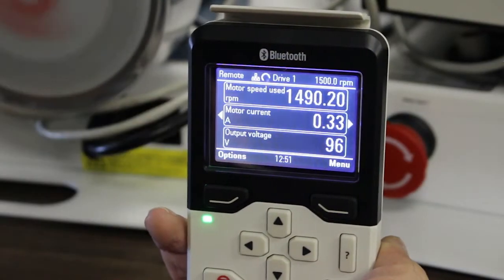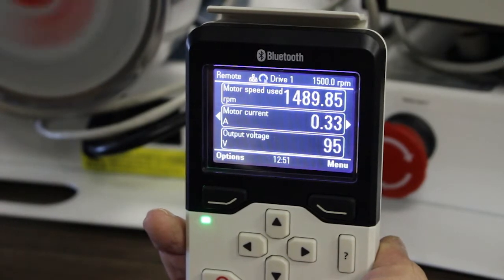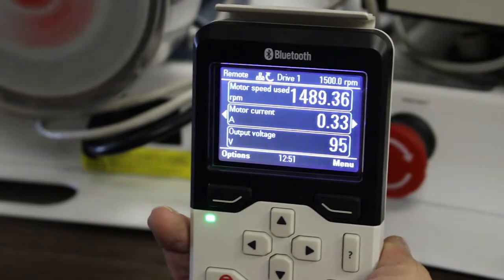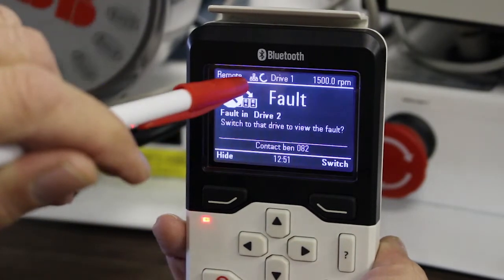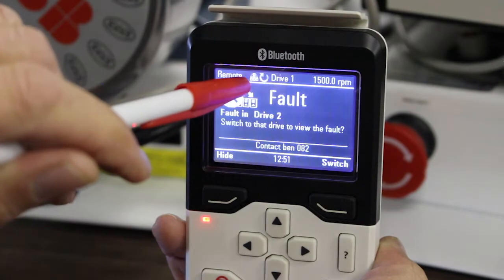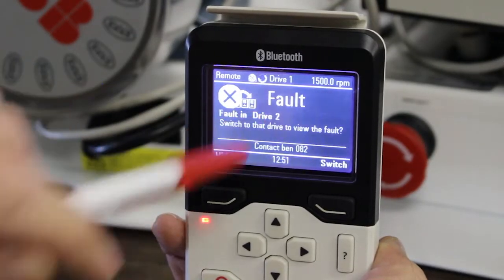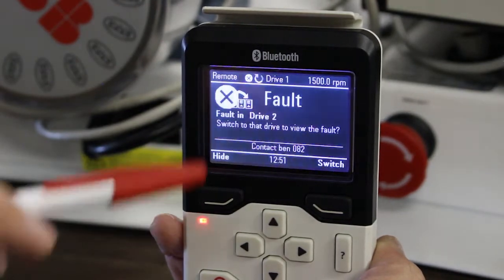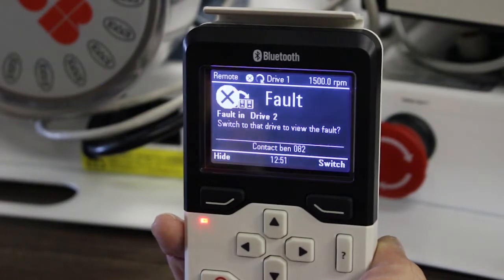I'm back in Drive 1. I've got Drive 1 running and Drive 2 running. Say for instance there's a problem in Drive 2 — Drive 2 trips. I'm creating a trip now. I can see the red light coming on indicating there's a fault. The network icon shows a cross — something is wrong. Drive 1 is still running fine. It tells me the fault is in Drive 2, or it could be Inverter 7 or Fan Inverter 5.